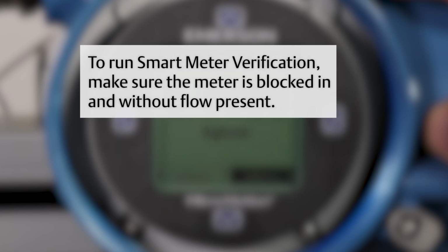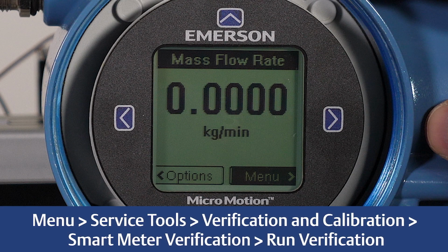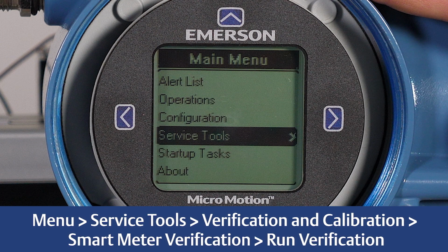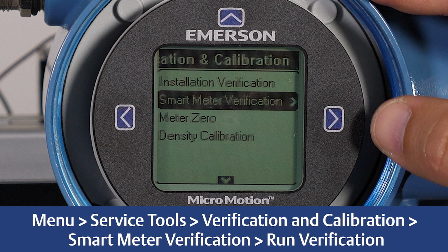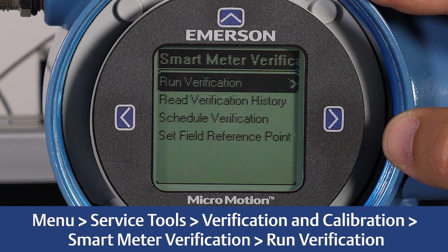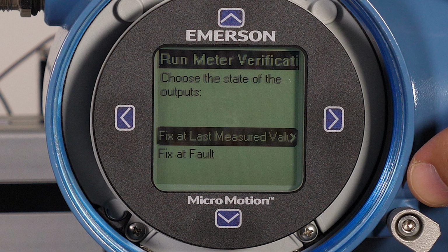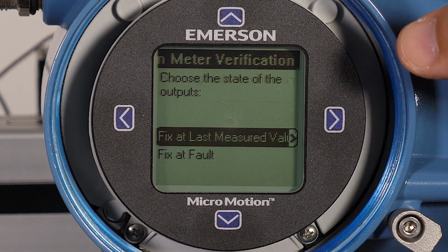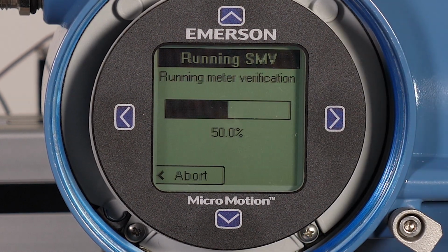To run smart meter verification, make sure the meter is blocked in and without flow present. Using the display, select Menu, Service Tools, Verification and Calibration, Smart Meter Verification, Run Verification. Choose the state of the outputs, either Fix at Last Measured Value or Fix at Fault. Select Last Measured Value to maintain current process reading or select Fix at Fault if you want to have an alert sent to the control system. We will choose Fix at Last Measured Value for this demonstration. Smart Meter Verification will run and report if the meter is working properly.